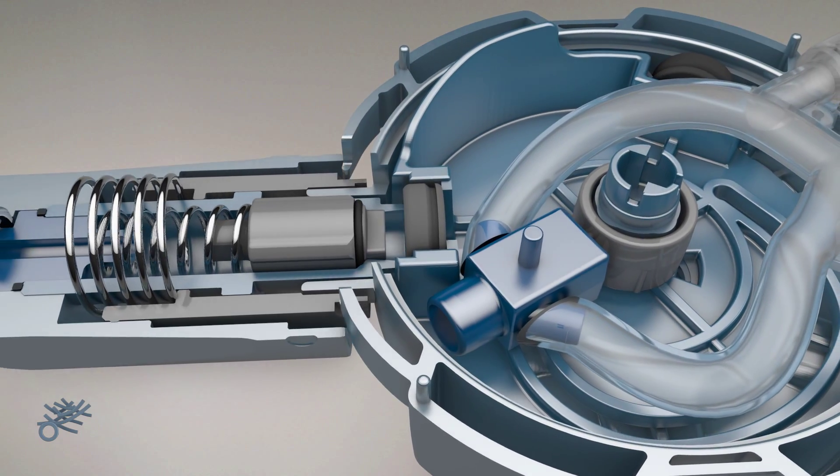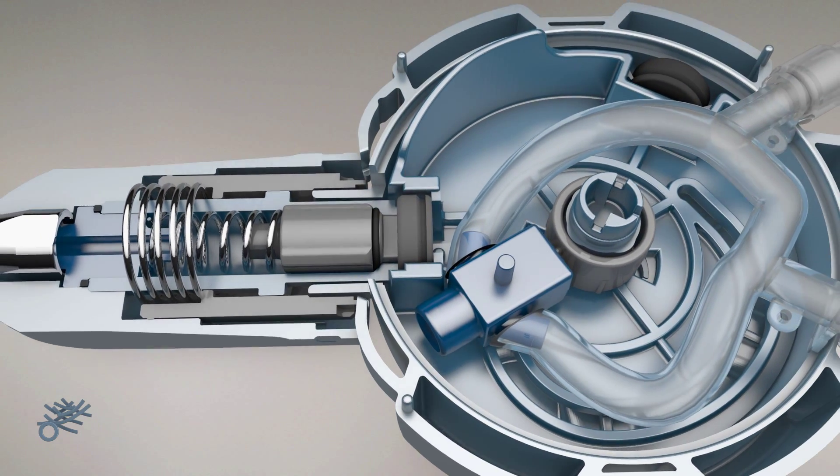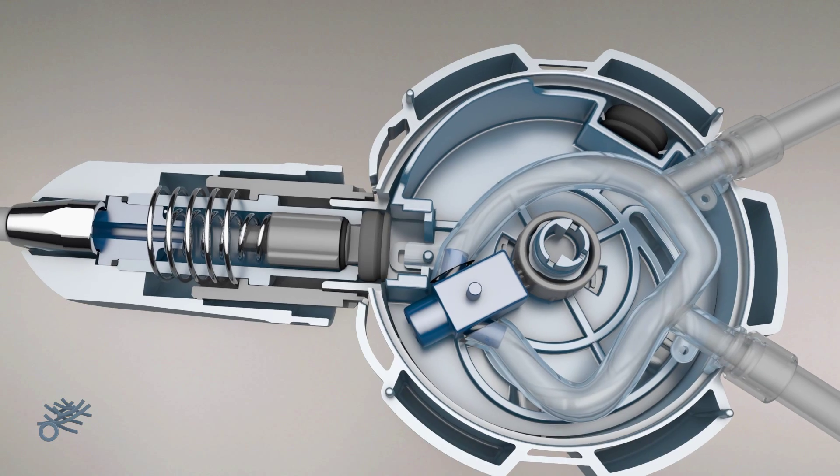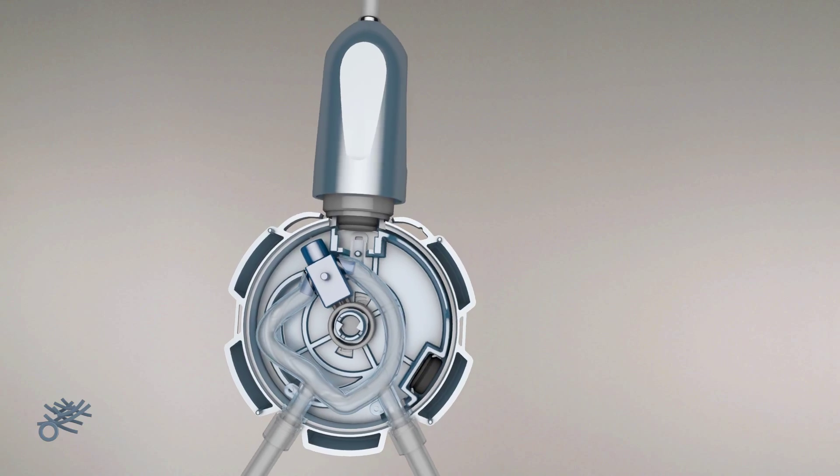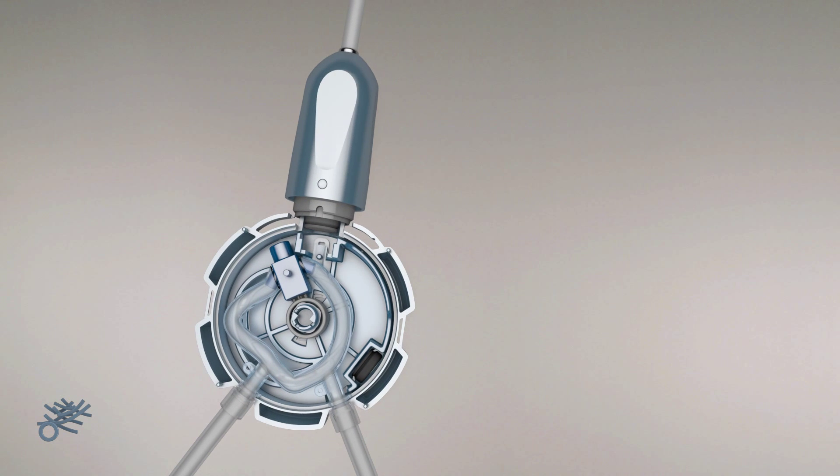Pushing the patient set towards the disposable unit fits the cap onto the patient set and deactivates the safety catch that has prevented unscrewing. The patient set can now be disconnected and the cycle terminated.